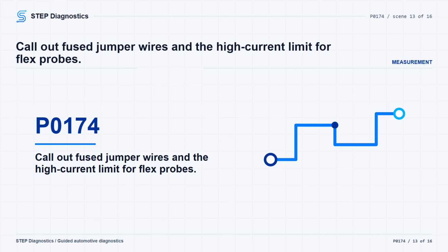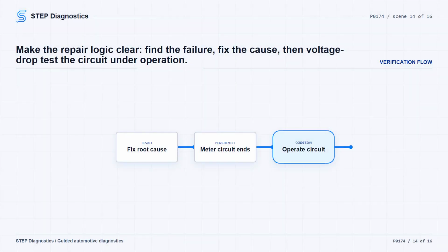When jumper wires are used, always use fused jumper wires. The recommended universal testing jumper wire fuse is 5 amperes or less, unless the load requires a larger fuse. Use flex probes or an equivalent to protect terminals. But remember, flex probes are not intended to carry high current greater than 5 amperes. Before repairing the failed circuit, find and examine the actual fault, correct the root cause, and repair any adjacent wiring that was damaged. Do not just add a new wire in parallel with the old one without understanding why the circuit failed.